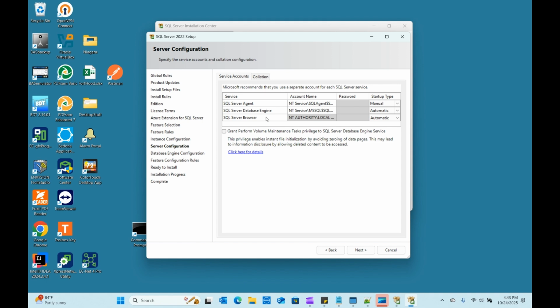The long and the short of it is you don't have to lock in your port. Like, the default port was 1433 for communicating with SQL Server. Now, of course, you could change that, and whatever you change it to, 2000, whatever, it'd stay that forever. But what SQL does now is if you don't lock in the port, every time the instance is started or restarted, it changes the port that it's communicating on. And the SQL Server browser is how Niagara knows to get that port. So automatic and automatic.